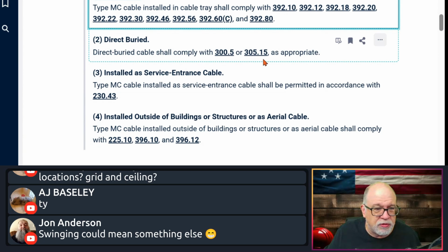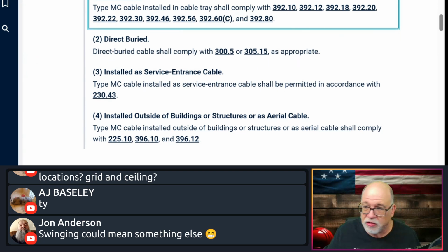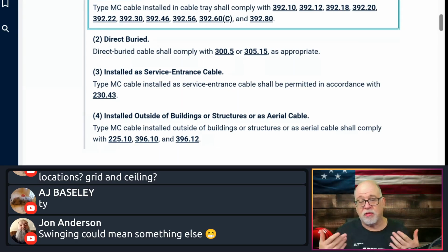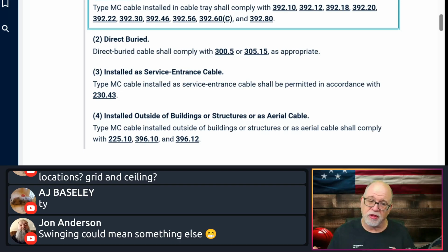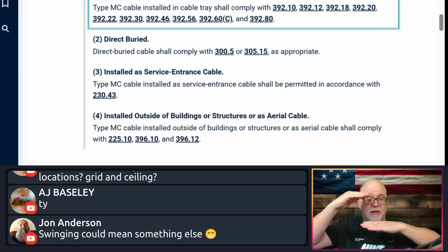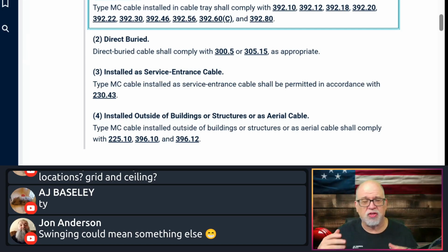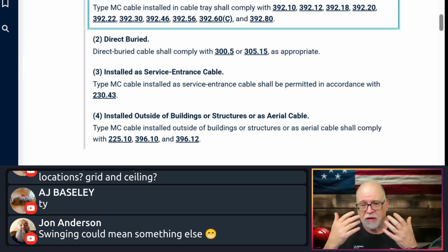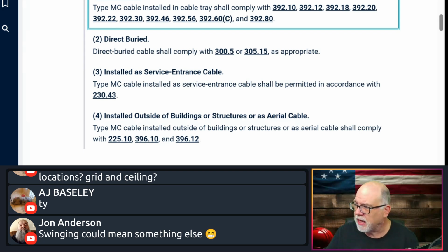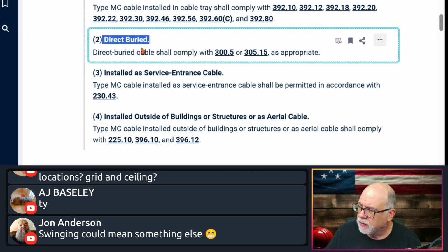And then when you're over 1,000 volts, 305 comes into play, because you can get MC cable in values that are over 2,000 volts, as well as what we probably use every day, the 1,000 volts or less, or 600 volt wiring methods, all those type of things. If it's going to be put in the earth, then it's still got to meet the depth of cover requirement at the top of the MC to whatever the finished grade is. That's your depth of cover. That's 300.5. And it also applies all those other rules as it emerges from grade and things like that. Okay, so you got to meet all those rules for direct burial.